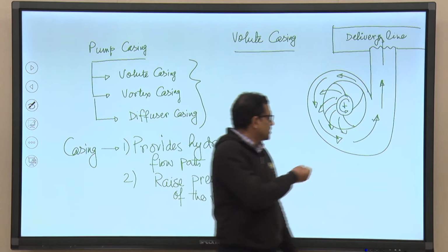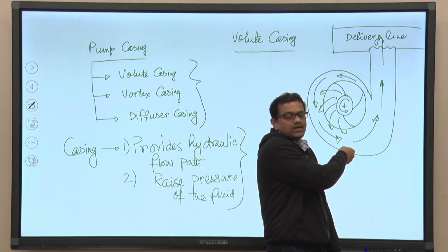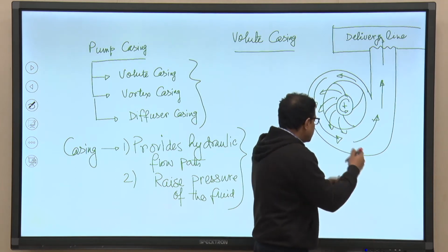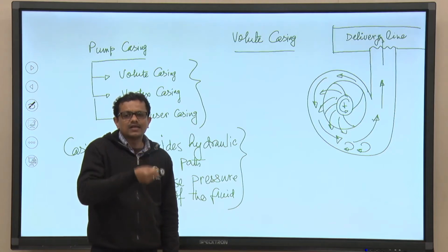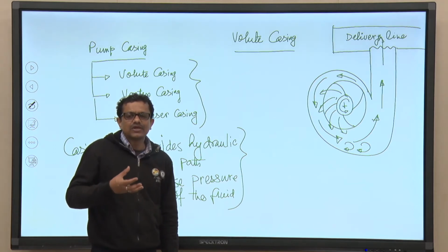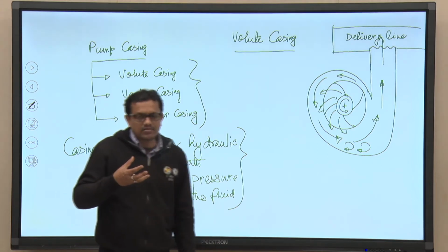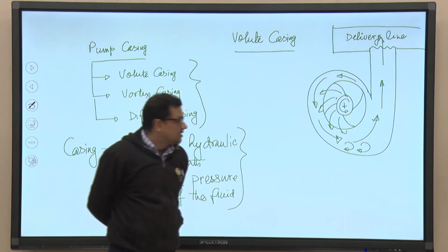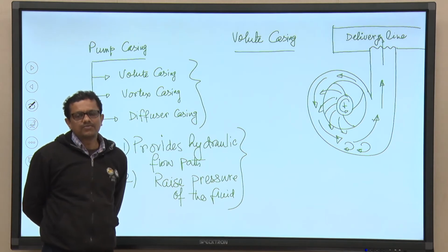So, our objective was to kill the kinetic energy and to convert into the pressure. Now, when eddies are formed, here eddies will be formed, here eddies will be formed. So, these eddies will try to extract energy from the main flow, as a result of which the efficiency of the pump, rather the net head which you are expecting from the pump will be reduced, and this is not favorable from the pump operation point of view.